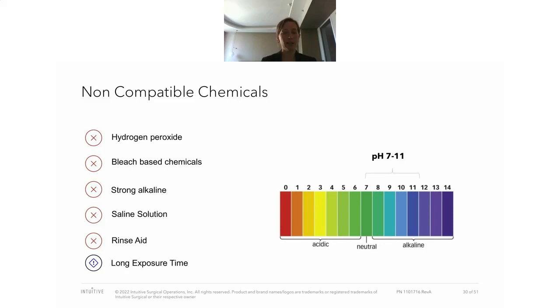And in particular for the automated pathway, where in some countries rinse aid is being used, the rinse aid is not reacting well with our instruments and that should be avoided. Even if you use the correct detergent at the correct pH, if the exposure time greatly exceeds what the manufacturer recommends, that could also lead to damage. So that is something to keep in mind.